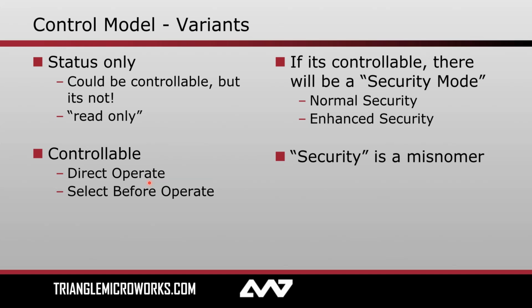Select before operate adds an extra step there. I first ask, I as the client ask the server, hey, is it okay if I kind of seize the controls? I want to make sure that no one else is trying to issue a control at the same time. Think of it like a reservation. The server can then respond and say, yes, you are now in control. Go ahead, tell me what you want to do, passing the baton, so to speak. So that's the difference between direct and select before operate.